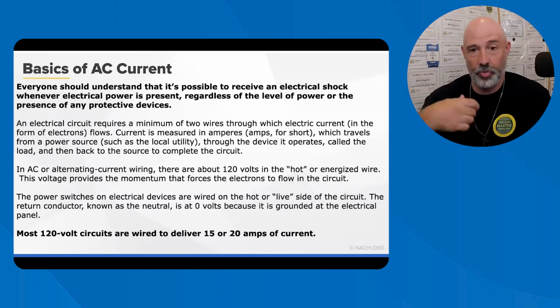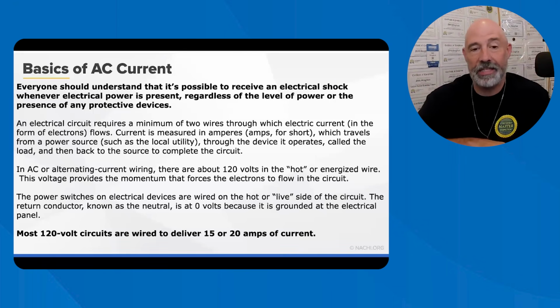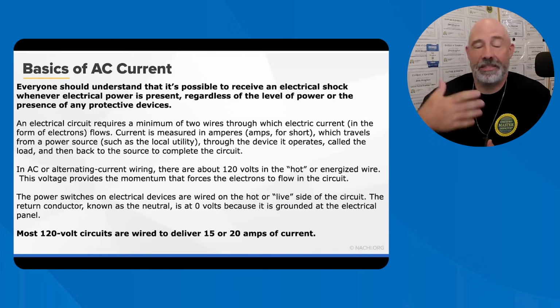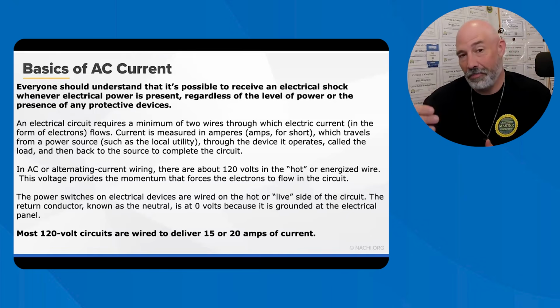That's enough to really jolt you. I can't tell you how many times I have been jolted because I thought I turned off the breaker and I didn't check it. You do it two times, you won't do it again. So always assume conductors are energized until you actually prove otherwise. Take your little meter and just make sure that it is not energized.